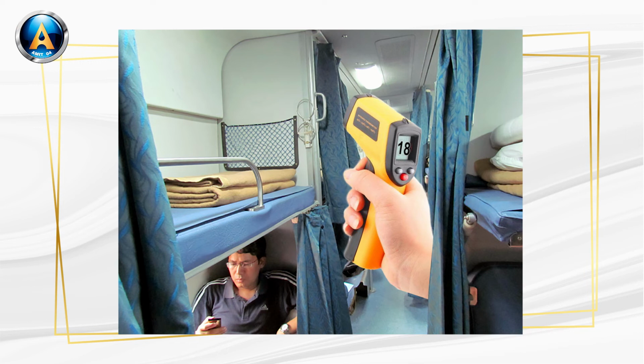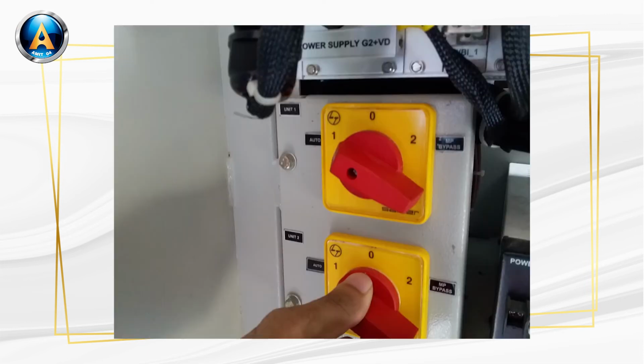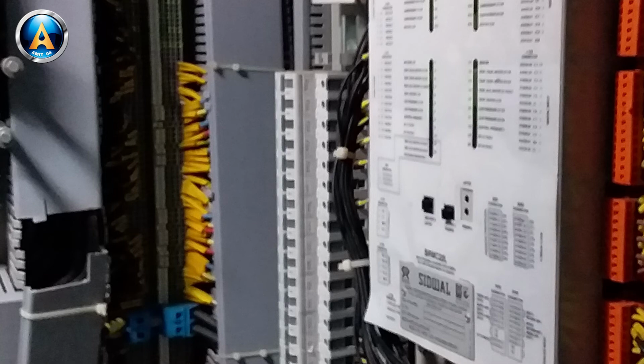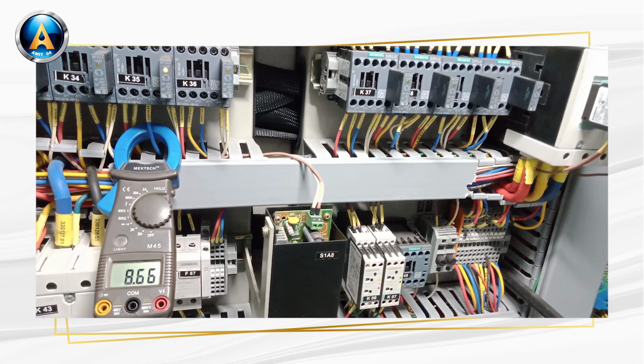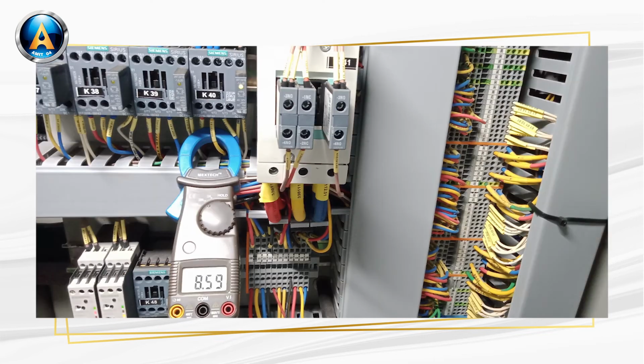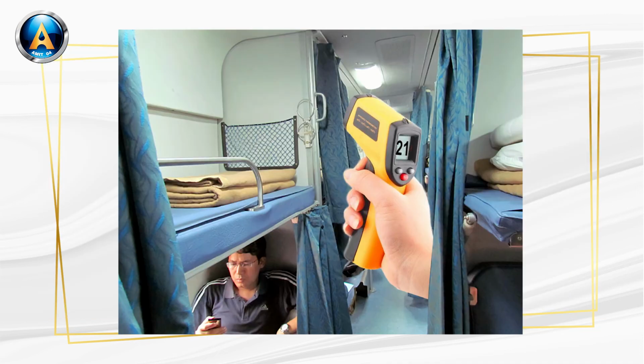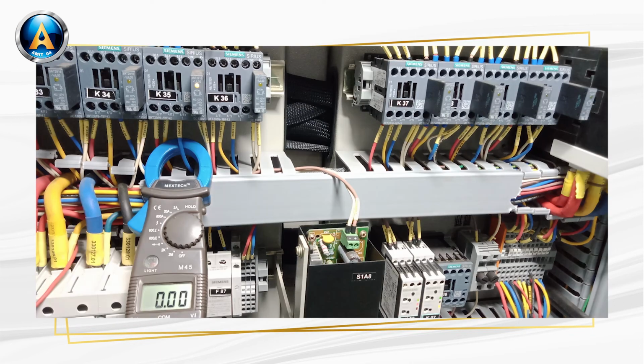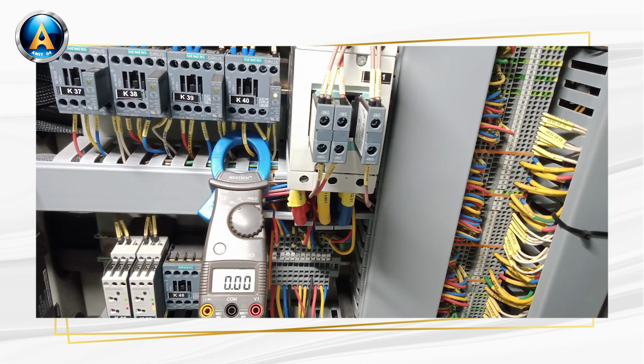When the inside air temperature reaches below 19 degrees centigrade, then you should run the microprocessor and check whether the K35 and K40 contactors are both being operated or not, and also check whether the K35 and K40 contactors are being opened or not at coach inside air temperature 21 degrees centigrade.